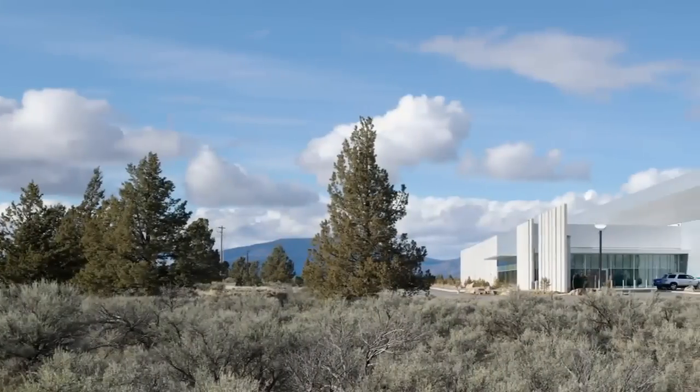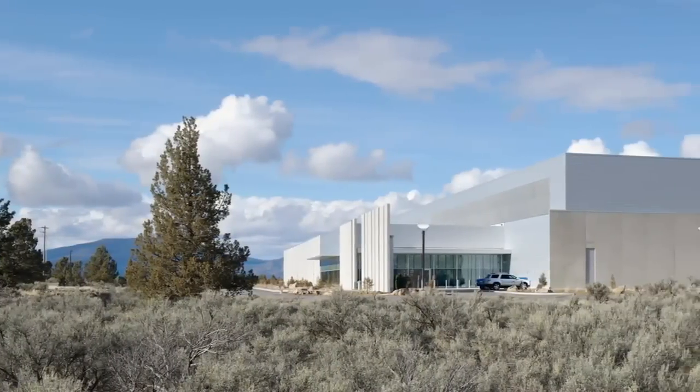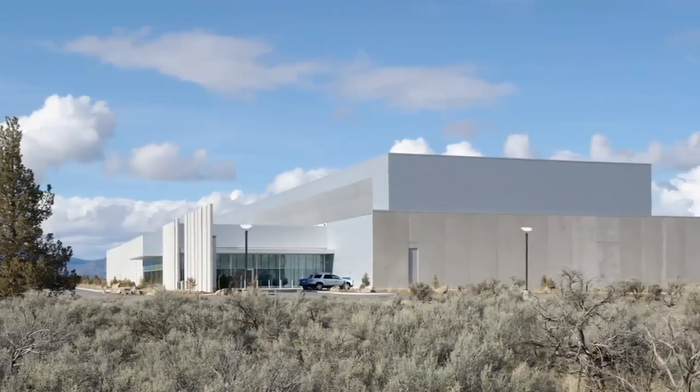Do I need to add moisture to it? How much of the warm air do I add back into it? If it's a really hot day, you don't recirc anything. Generally, you just send it out because it's generally hotter than the air actually coming in, and then all you're doing is cooling.